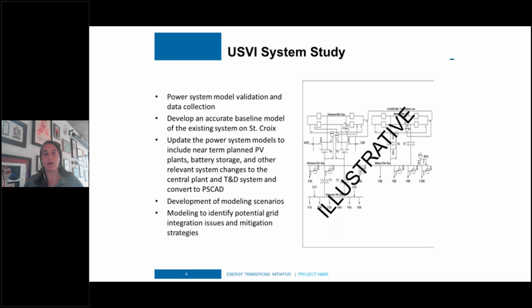So as part of their recovery, the utility in the Virgin Islands is looking at diversification of their generation. They are primarily running on fossil units that are dual fuel capable, so heavy fuel oil as well as liquid propane gas. So they are upgrading their generation fleet to smaller, more flexible generators that can then accommodate a higher level of variable renewable energy on their system. So they're looking at installing a significant amount of solar PV as well as battery storage in addition to the solar PV that they already have installed on the island of St. Croix.